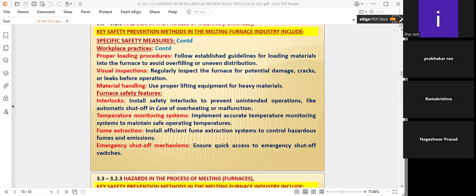If there is any malfunction, we have to confirm which is right, the local gauge or the distributed control system. You have to use expertise to implement immediate steps and ensure the interlock works properly, so the temperature is maintained at the optimum design without hindering furnace operation. That comes with experience.